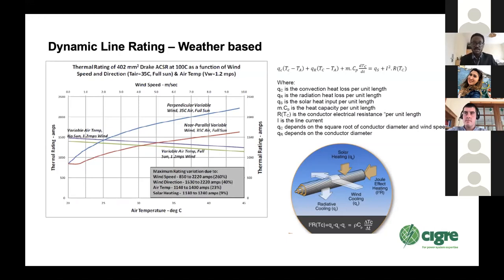And so, if we know the actual weather conditions along the line, we could use several standards, for example, the CIGRE 207 standard, to determine the maximum amount of current that can be passed through the line without violating the ground clearance limitations. For example, as you can see in front of me, there are several factors that could be considered to optimize the amount of current in the line. One of such factors is the wind speed. We can also look at the wind direction, the air temperature, solar heating. But I just want to point out, for example, that if you optimize the wind speed, you can improve the capacity of the line by up to 260%. But this is usually not the case, because in order to do that, you have to get wind speeds of about 10 meters per second. And usually at the height of overhead lines, the wind speed is not that high. But you could get up to a 50% increase in the capacity of the line.